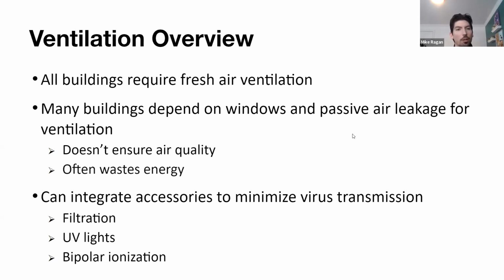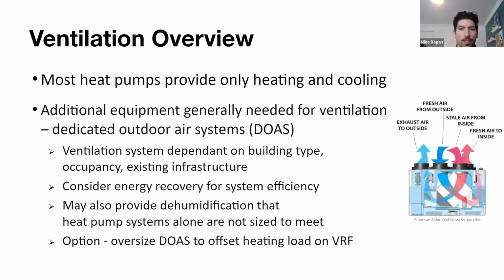That's another element we can build into our designs. It's important to note most heat pumps are designed to only provide heating and cooling to the system, just heating and cooling. That's the H and the AC in HVAC. Additional equipment is typically necessary for that ventilation aspect. And that's typically done in the form of a dedicated outside air system, or a DOAS system. So we certainly want to take a look at the existing infrastructure, the layout of the building, in order to determine how we're going to integrate ventilation with our equipment.